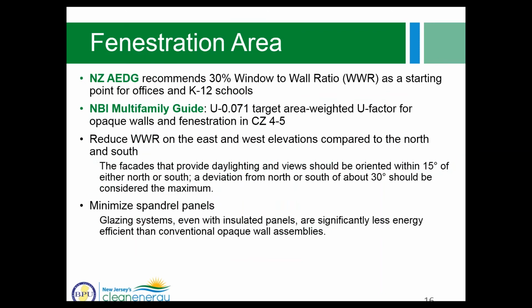So when it comes to improving envelope, perhaps one of the biggest opportunities is related to fenestration area and orientation. The Net Zero Advanced Energy Design Guide recommends 30% window to wall ratio as a starting point, and window to wall ratio is the ratio of vertical fenestration area to gross above-grade wall area. So this is the starting point, and then you can walk from there to see how increasing this fenestration area affects building performance.